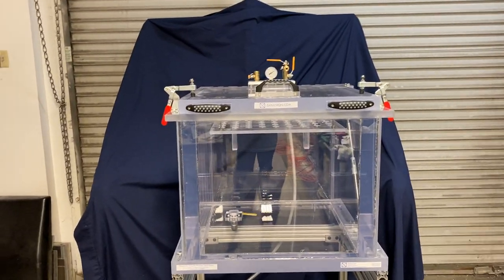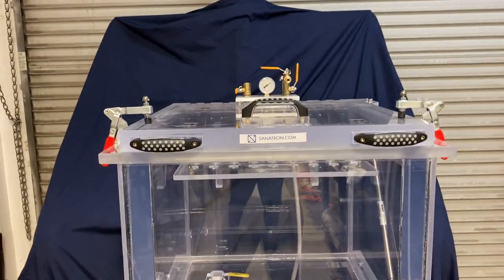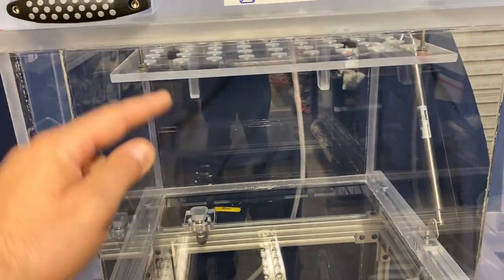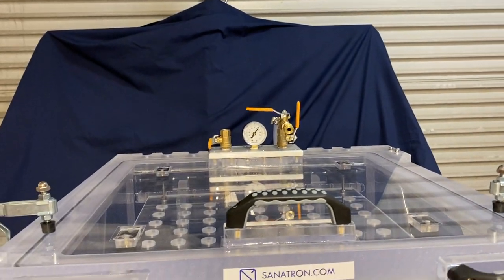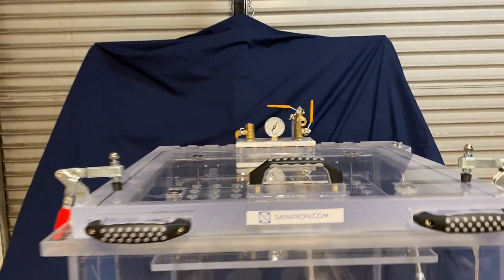So it's going to take a minute or so to get to about 15 inches of mercury, it will take about a couple minutes to get to about full 25 inches of mercury. And essentially this whole chamber is empty. When you have water you will decrease the volume so the pump down time is going to go much much faster.